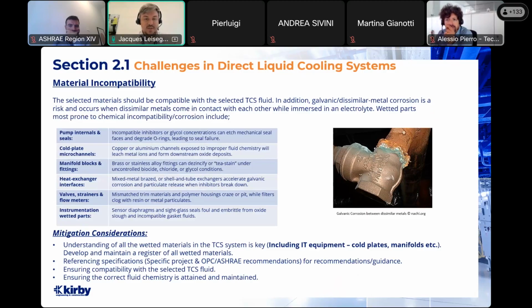Referencing specifications such as project specifications, OPC and ASHRAE recommendations. Tommaso referenced the TC 9.9 committee. They've got a lot of good documentation in terms of what materials should be used in these systems. Ensuring compatibility with the selected TCS fluid, and then very important, ensuring that the correct fluid chemistry is attained when you're getting that system flushed and started up, and then also ensuring that chemistry is maintained through the life cycle of that project, of that system.